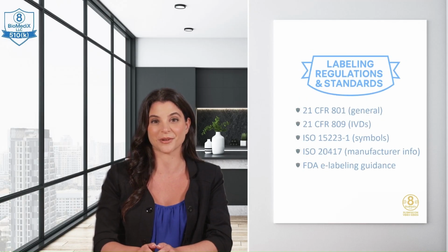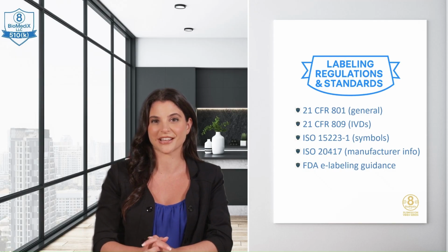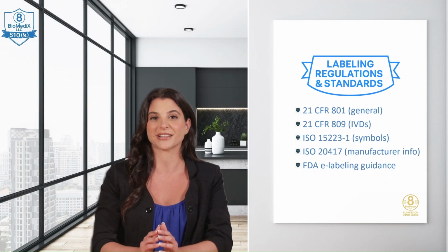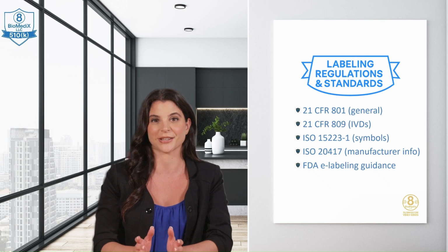Labeling also needs to comply with 21 CFR Part 801 General Labeling, Part 809 for IVDs, ISO 15223-1 Symbols, and ISO 20417 Information to be supplied by the manufacturer. If your device is prescription-based, don't forget the RX-only statement. And if you're using electronic labeling, follow the FDA's guidance for digital formats. eSTAR provides structured fields to confirm you've met these requirements. Use clear language, include warnings and precautions, and never imply FDA approval. If a claim isn't backed by data or a recognized predicate, leave it out.